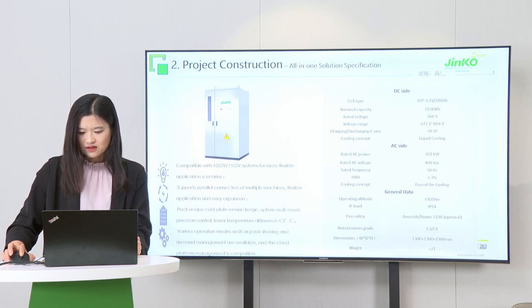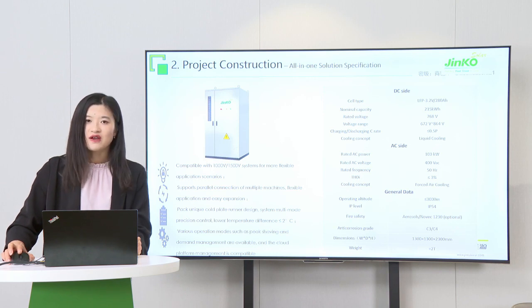At the DC side, the nominal capacity is 215 kWh, the rated voltage is 768 volts, and the charging or discharging rate is less than 0.5 P. While at the AC side, the rated power is 100 kW, the rated AC voltage is 400 volts, and the rated frequency is 50 Hz. Its operating altitude is less than 3,000 meters and the protection level is IP54.